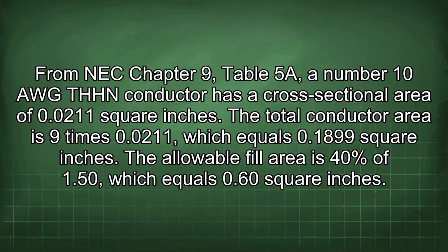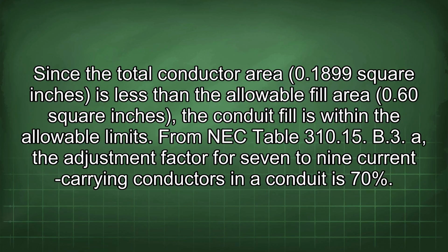The total conductor area is 9 times 0.0211, which equals 0.1899 square inches. The allowable fill area is 40% of 1.50, which equals 0.60 square inches. Since the total conductor area 0.1899 square inches is less than the allowable fill area 0.60 square inches, the conduit fill is within the allowable limits.